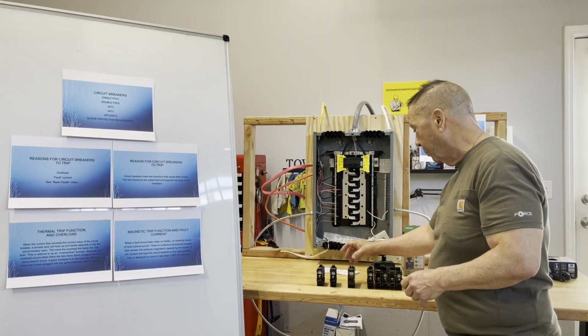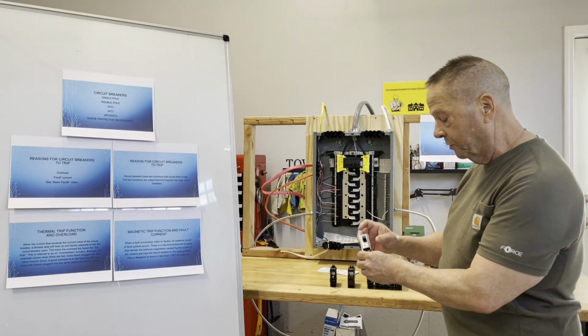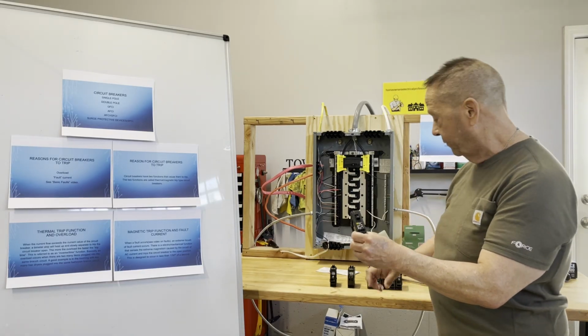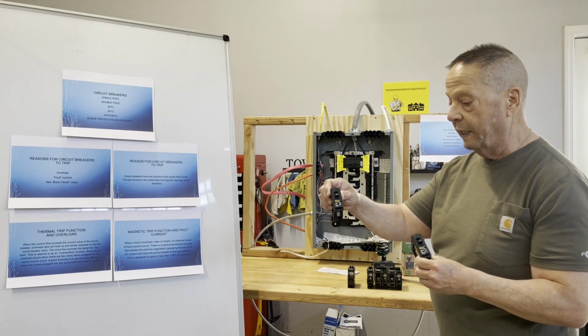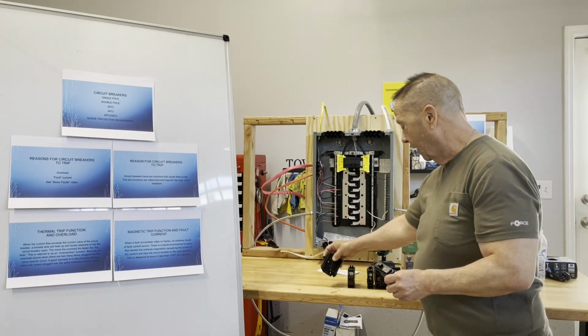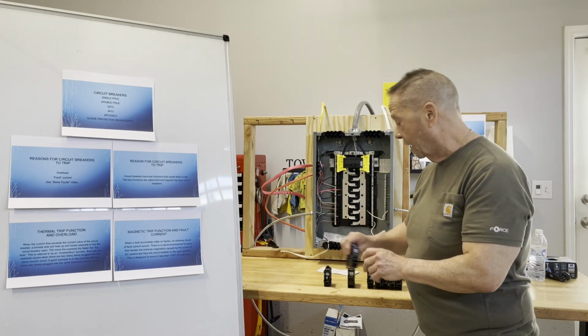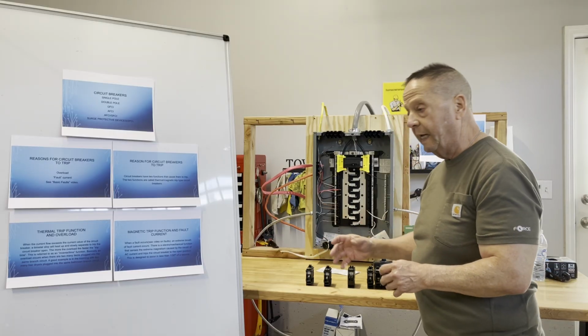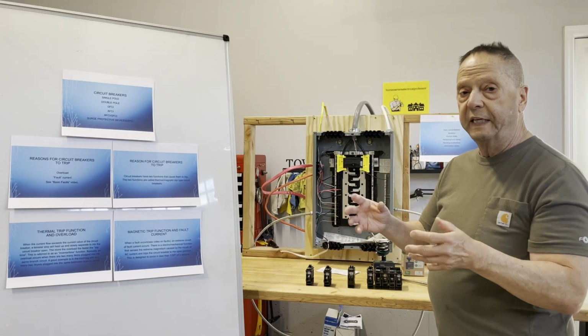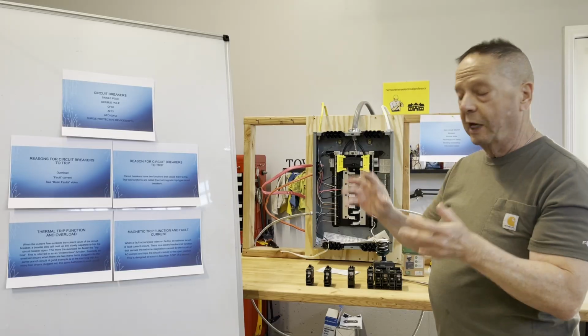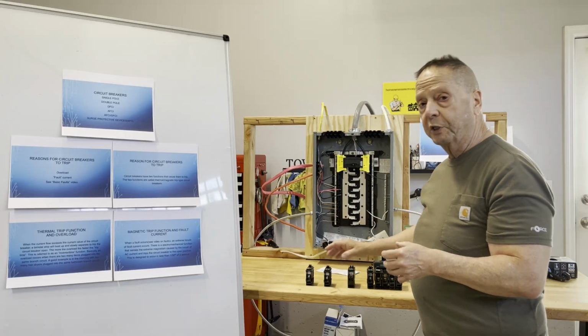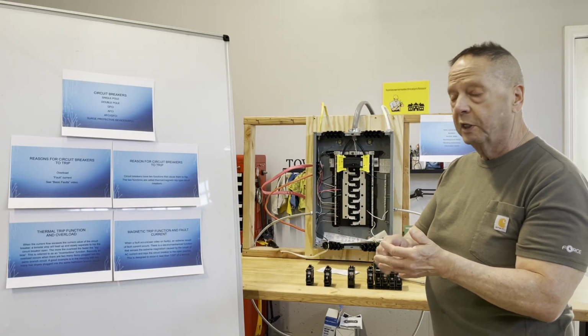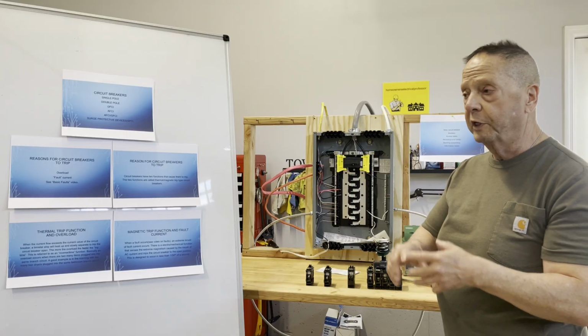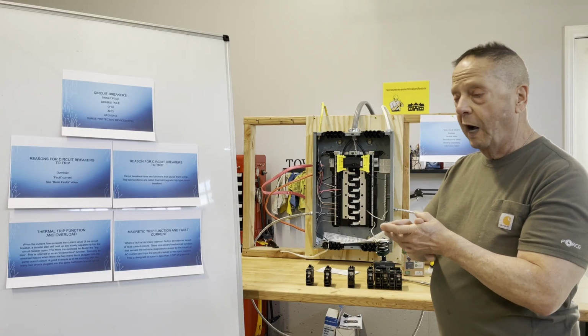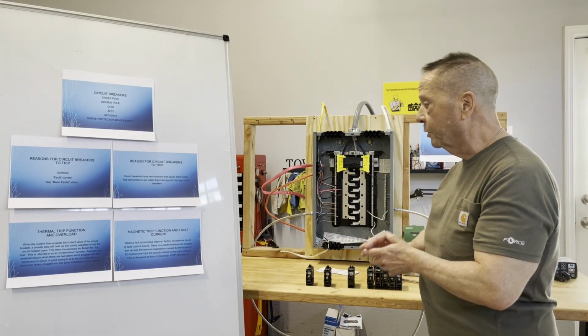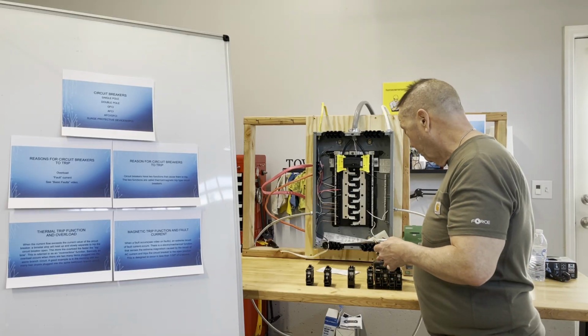Now, single pole circuit breakers. Basically, they will come in either a 15 amp or a 20 amp variety, okay? I went over this under wires and conductors, where basically your 15 amp breaker is going to be your convenience receptacles and your general lighting. The 20 amp is going to be more specialized for kitchens, bathrooms, laundry, and out in your garage they require a 20 amp receptacle. Okay, we also have double pole breakers.